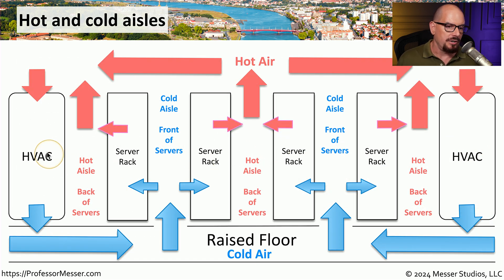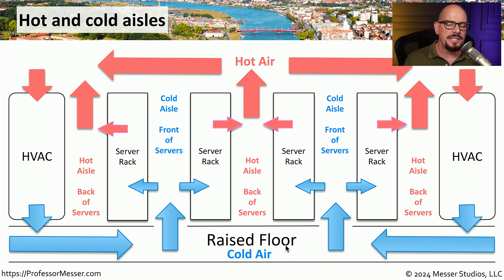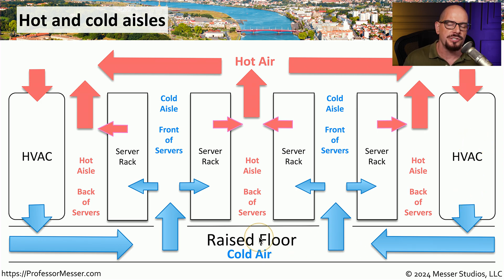Here's a cross section of a data center. On the left and right sides we have our HVAC system, and in this particular environment the cold air is going under the floor and the hot air is being pulled out of the ceiling. The cycle starts with the HVAC creating the cold air, which goes underneath the floor in this raised floor environment. There are vents and holes in the floor that allow the cold air to flow into a cold aisle — this is often the front of the servers, and the servers are pulling in that cold air to cool the inside of the server. Once that air is heated up, it's sent out the back of the server into a hot aisle, and that hot air rises into the ceiling where it's pulled back into the HVAC, recooled, and the entire system repeats.